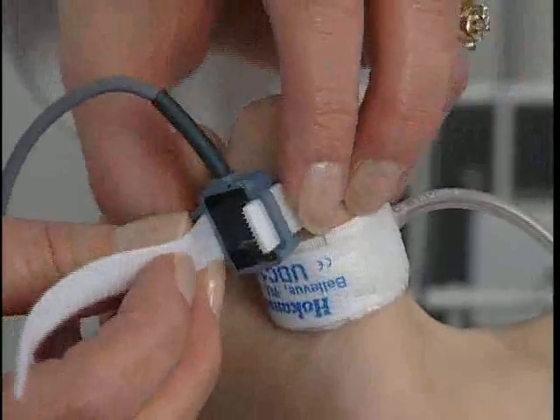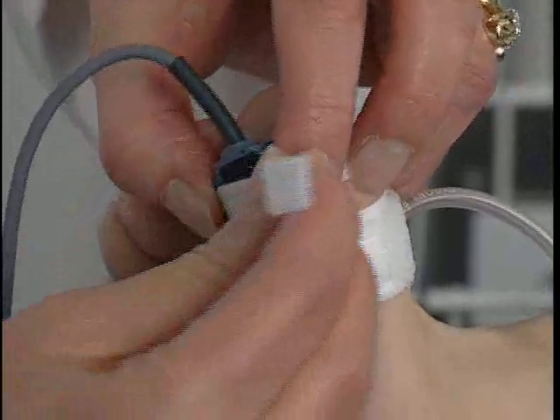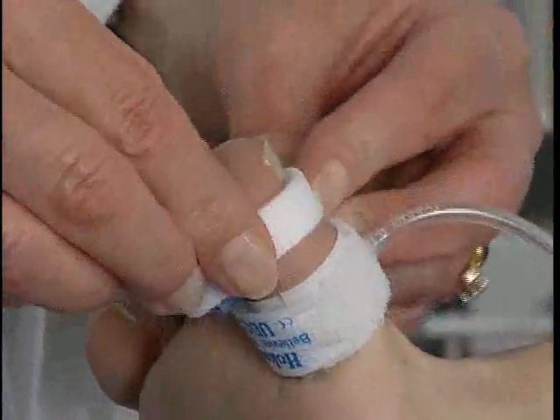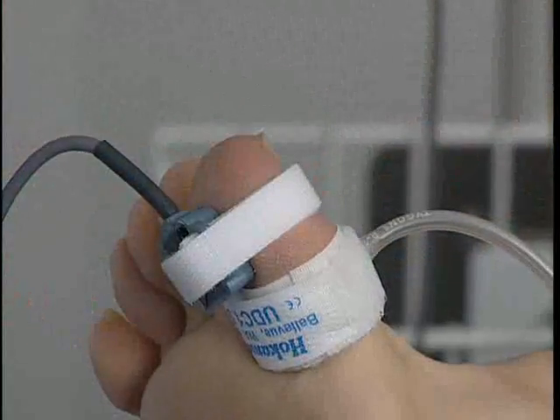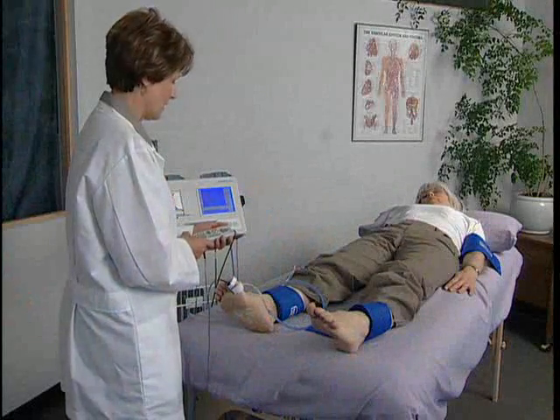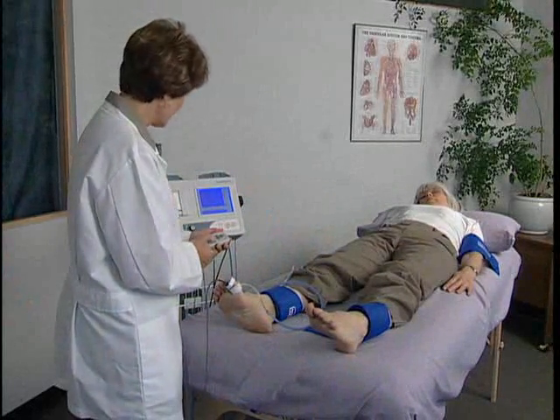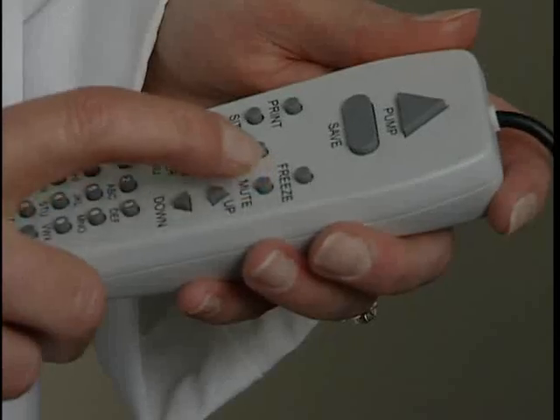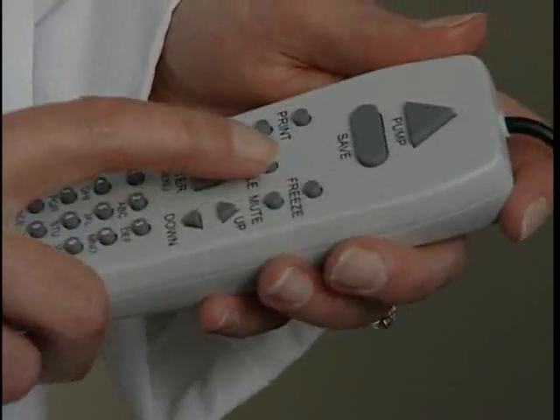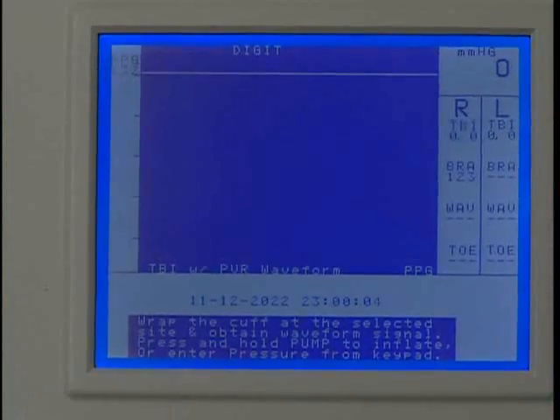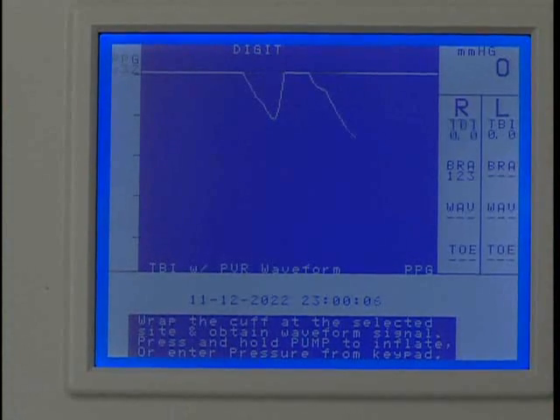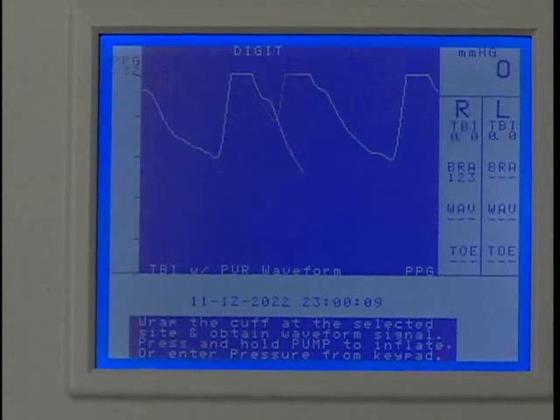Attach the PPG probe to the toe distal to the cuff with the blue side of the probe against the skin. Again, the probe should be snug but not too tight. The patient must be still. Wait several seconds for the waveform to stabilize. Press Scale one or more times as needed to adjust the vertical scaling to obtain a waveform as large as possible without clipping at the top.